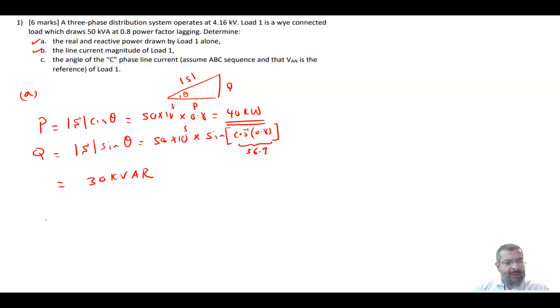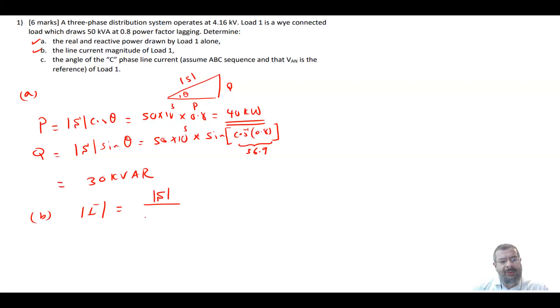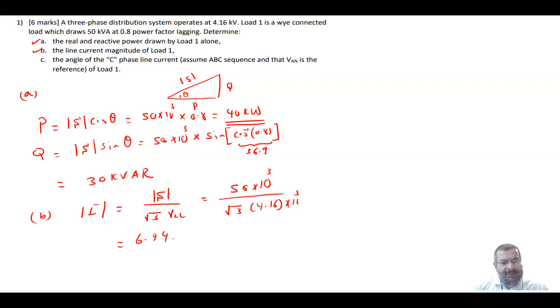Part B: find the line current magnitude of Load 1. The current magnitude I is equal to S divided by root 3 times the line-to-line voltage. So your S is 50 times 10³ divided by root 3 times 4.16 times 10³, and this will give a current equal to 6.94 amps.